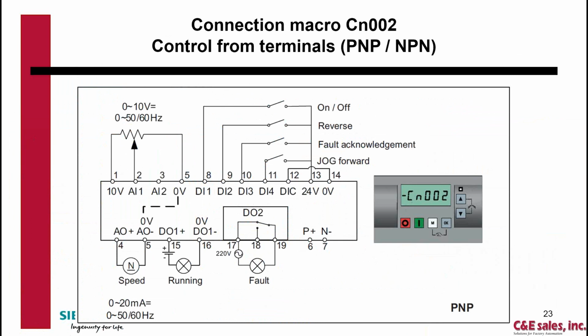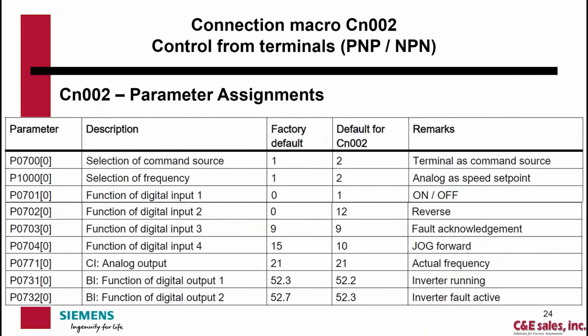Also notice this jumper here between 12 and 14. The jumper is going to determine whether it's PNP or NPN. So if I connect it to 0, I'm using PNP, or 24-volt source as the input. And then this shows you the parameters that populate when Cn002 is selected. So you're looking at terminal as command source, analog as speed set point, and function of the digital inputs. Number 1 is on off. Number 2 would be set to 12 for reverse, but those are the parameters that it populates for you.